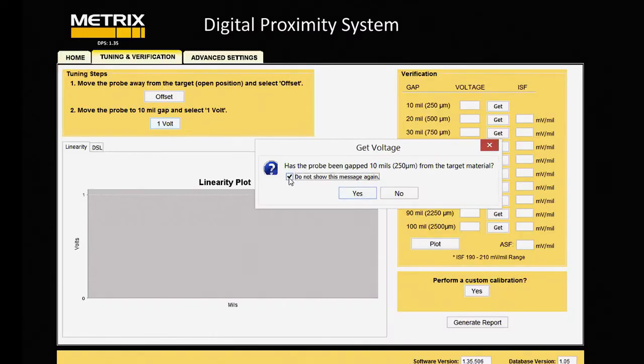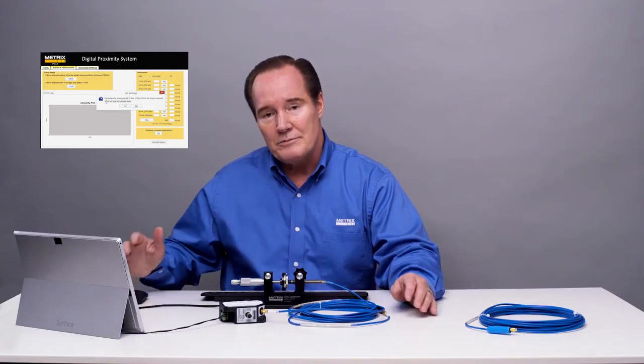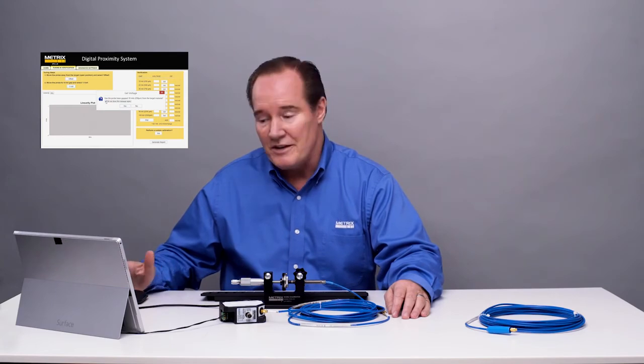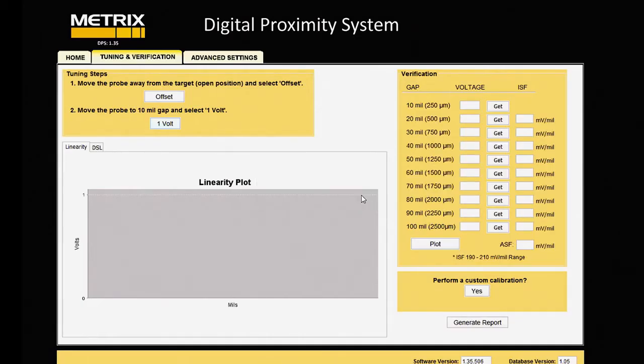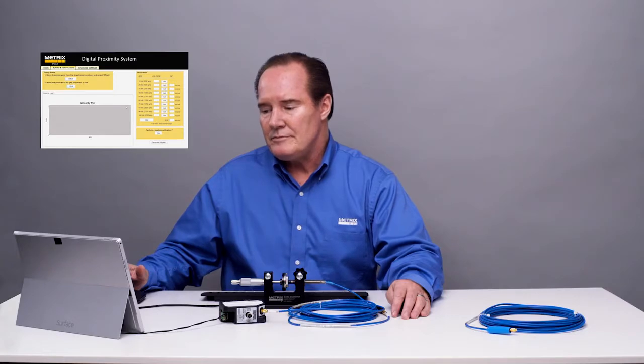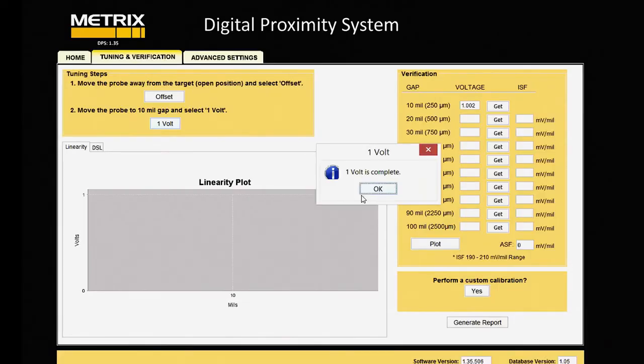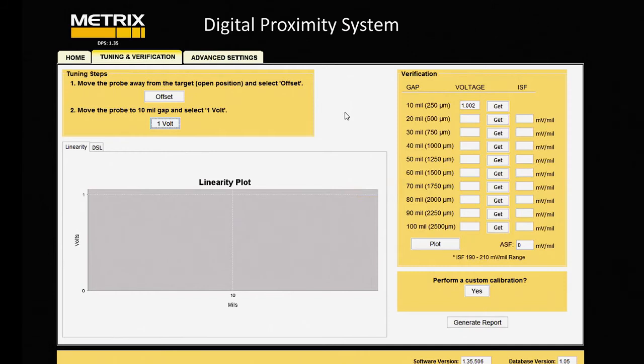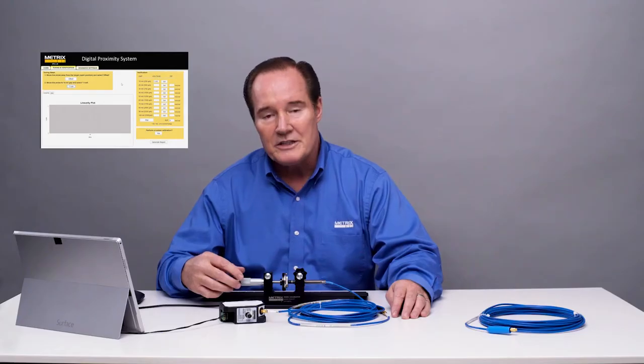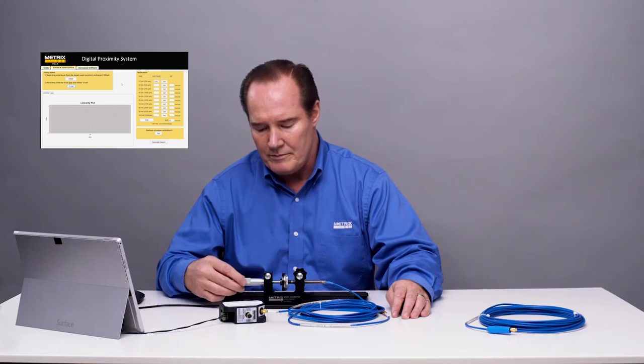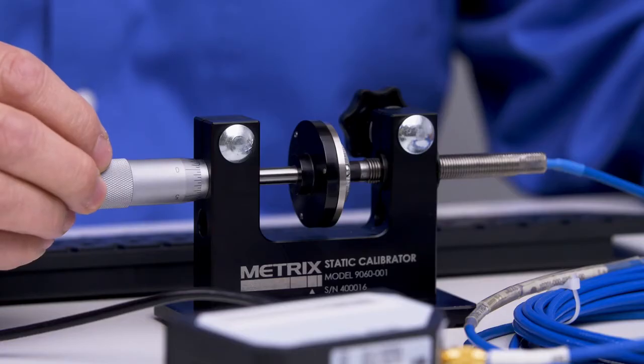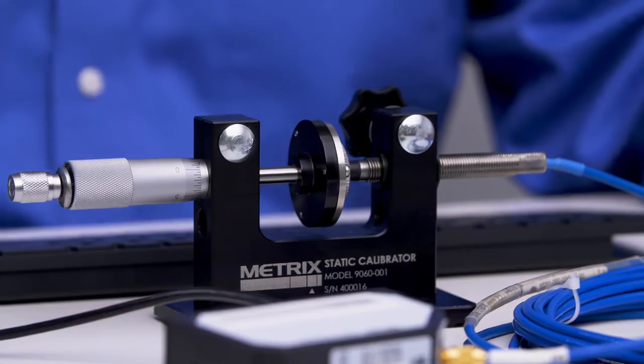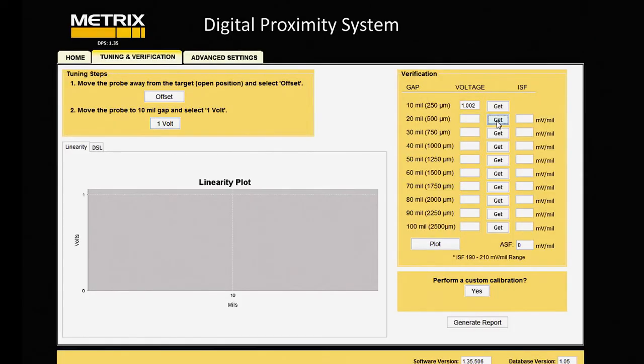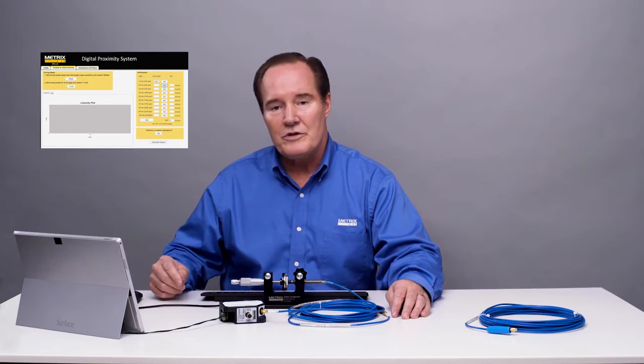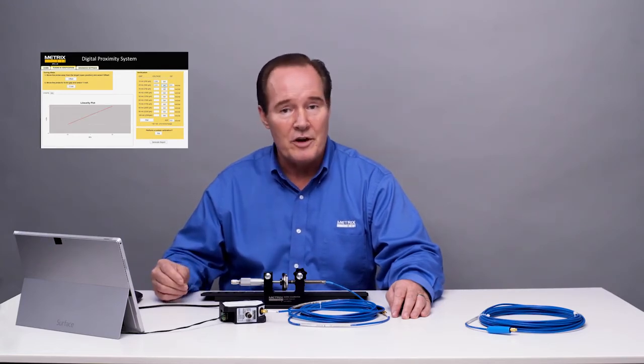And we know we're not having the factory do this. We cut this cable ourselves and we put a connector on. So we have to basically adjust the electrical parameters in the system. So we'll say yes, and we should get 1 volt. Looks good. And then we'll move the dial micrometer in 10 mil increments and take data along the way. So I'll move it to 20. Say get. And we'll do the same thing all the way to 100, and then we'll look at our results.